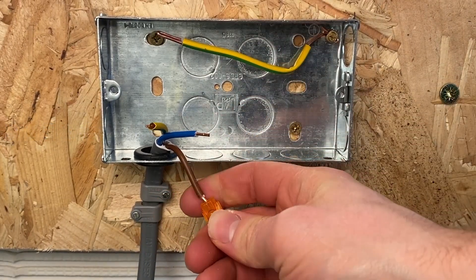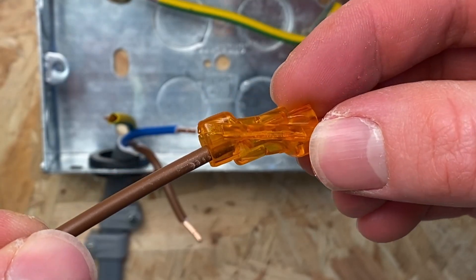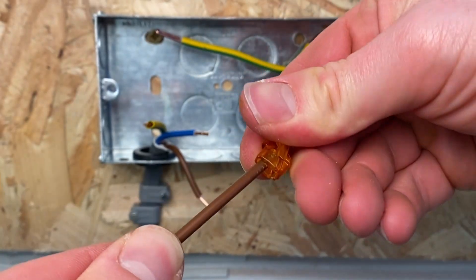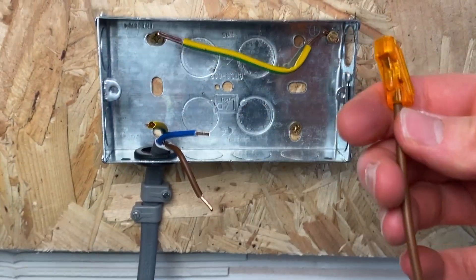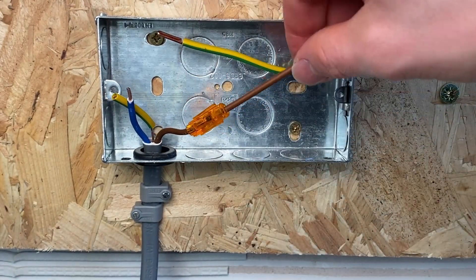Another option is the Ideal inline connector. These are just push-on but they don't easily come off once they're on. Push your cable in - same as the Wago, you feel it take - and you can see just in there where your sheathing ends. Pulling on it quite tight, that's a nice secure connection. Then the same onto your other piece of cable. You've got a nicely extended piece of cable there, and you can put quite a bit of force on that and it's not going anywhere.